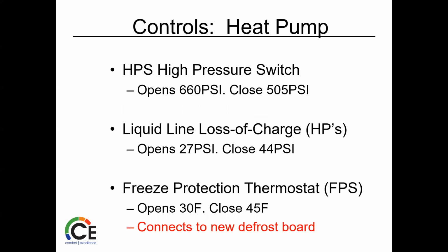High pressure switches, the majority of them open at over 600, close around 500. Liquid line opens at 27. That's the loss of charge one, closes at 44. Obviously, if that one's open, you've got a big problem, right? Freeze protection opens at 30, closes at 45. So it does wait till it gets a little past what we consider freezing before it closes or opens, forgive me. And that connects on the defrost board.